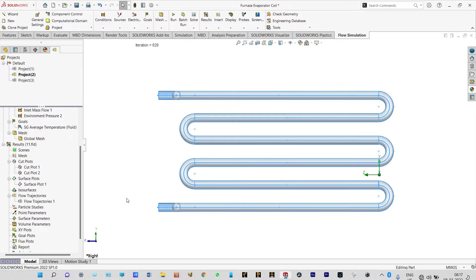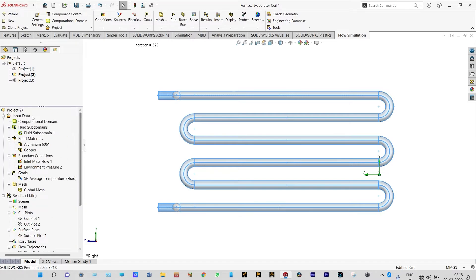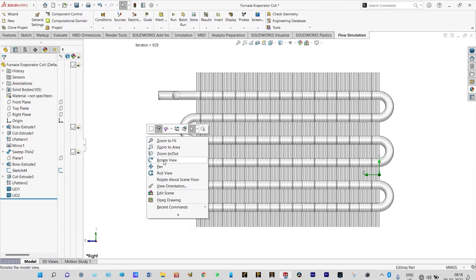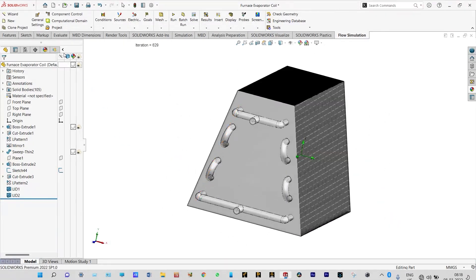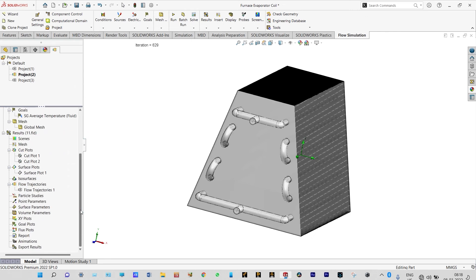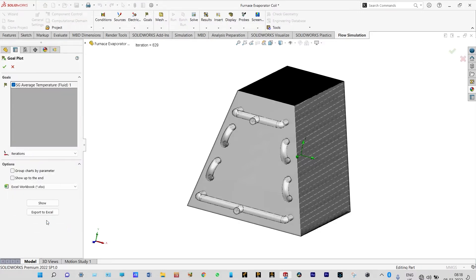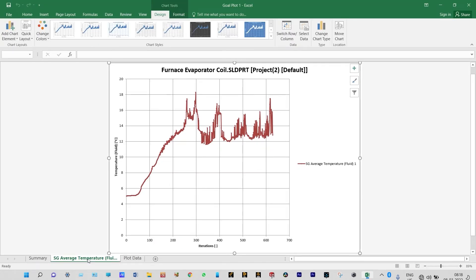Next we need to see the goal plots and we will have a complete view of the model. Insert goal plots — we want to see our results in the form of graphs, so we can transfer this to Excel. We have only one goal: temperature at the exit of the copper tubes. After 629 iterations, we got the final temperature of freon at the exit location, which is 12.798 degrees Celsius.